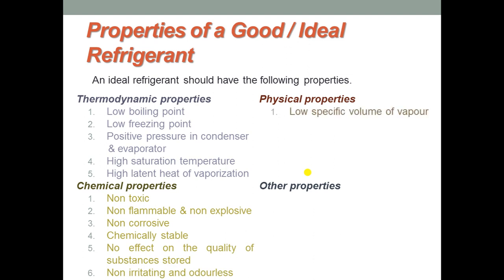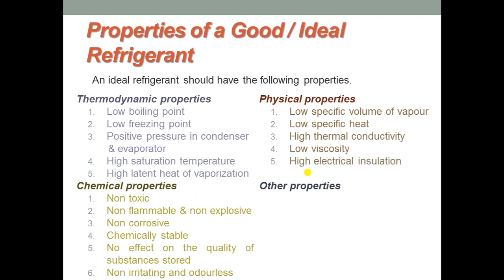The physical properties are: first, low specific volume of vapor so that it occupies minimum space, thereby keeping the compressor capacity to a minimum and pipe diameter relatively small. Low specific heat is the second physical property. The third is high thermal conductivity, so that heat transfer takes place easily. Low viscosity for easy circulation of the refrigerant. And high electrical insulation.